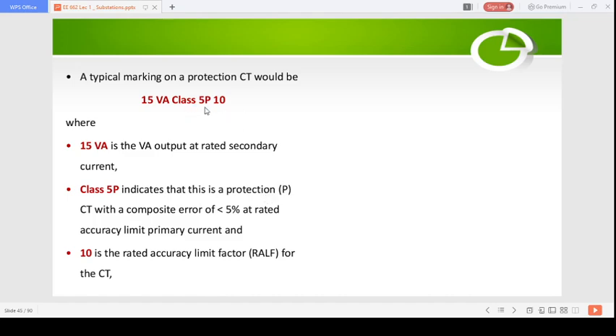Okay, and the class 5P indicates that this is a protection CT. The P indicates that it is a protection CT with a composite error of less than 5% at rated accuracy limit primary current. So this 5 represents that it's class 5P, which means a protection CT with composite error less than 5% at the rated accuracy limit. And 10 is the rated accuracy limit factor, RALF, for the CT.